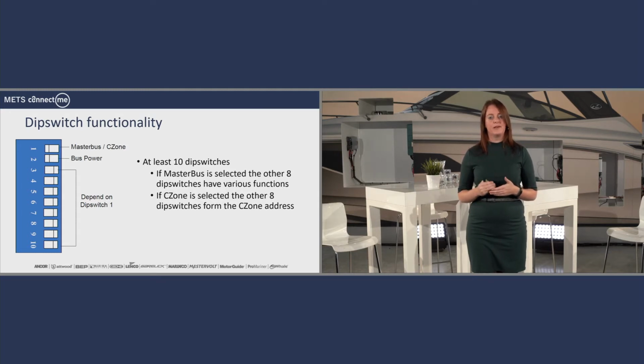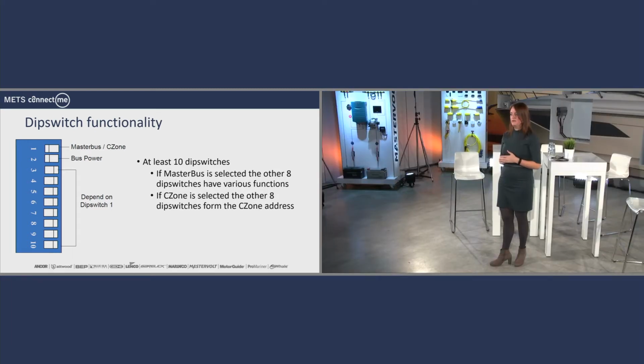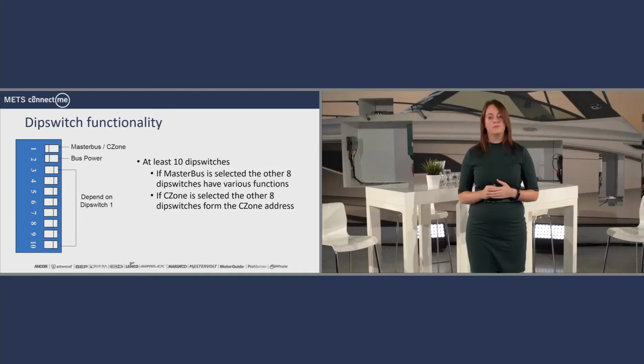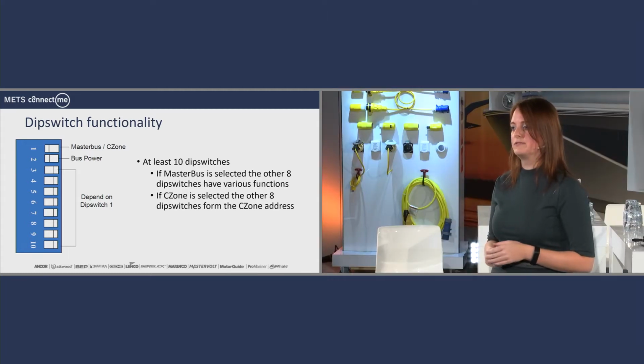Dip switch 3 to 10 then become the address, which is unique within your CZone network, similar to what you've seen with all CZone devices. If you set dip switch 1 to Masterbus, then you can set dip switch 2 to on, and dip switches 3 to 10 become configuration options you're used to from our Mastervolt devices. For example, dip switches 3, 4, and 5 will always be the selection of battery type for a charging device. You'll find this with Charge Masters, Combi Masters, and in the future with more devices as well.